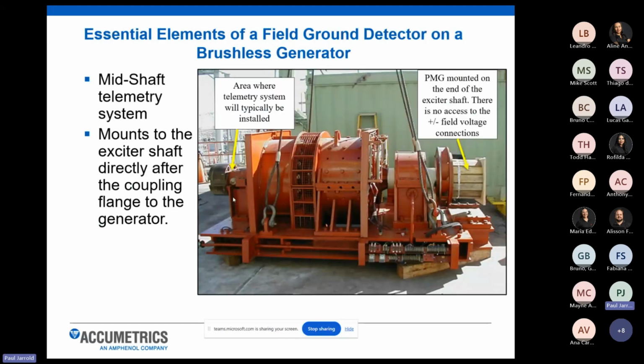So the EFRAM system comes in 2 product sizes or 2 product packages, the mid-shaft system and the end-of-shaft system. So we're going to discuss our mid-shaft system first. This system is designed for larger brushless exciters. Usually we see these on a Siemens Westinghouse type of brushless exciter, very large machines, maybe 500 megawatts or greater. In those machines, they induce the field voltage using a permanent magnet generator on the end of the exciter, and we don't have direct access to the field windings on the end of these larger exciters.